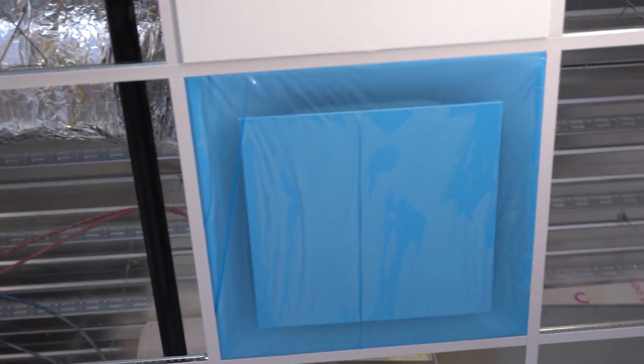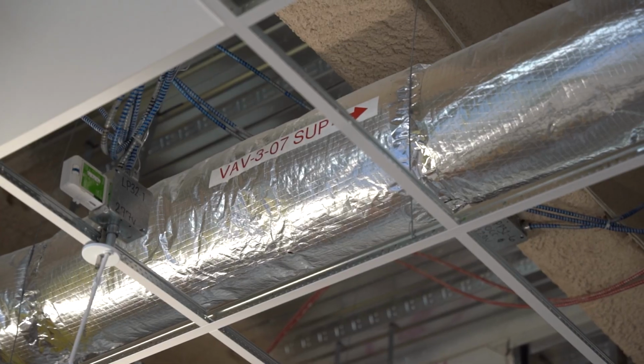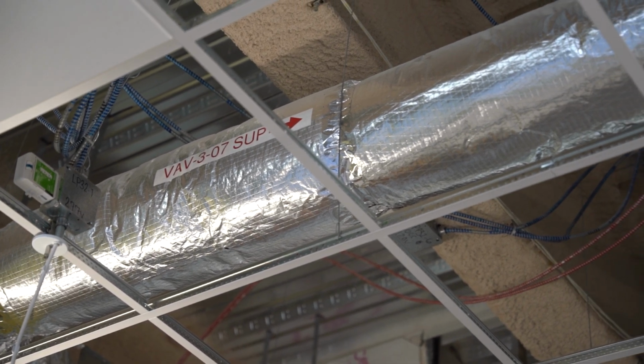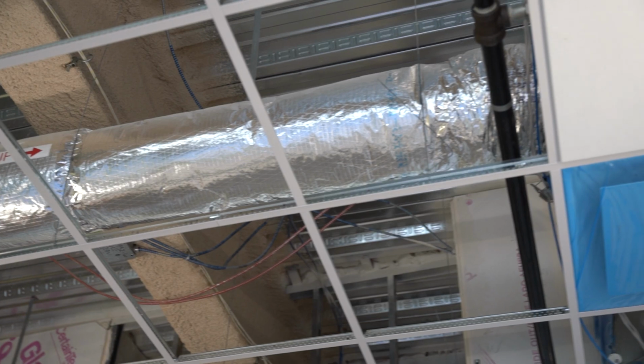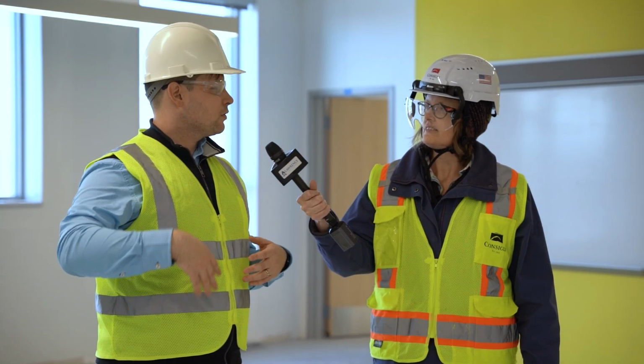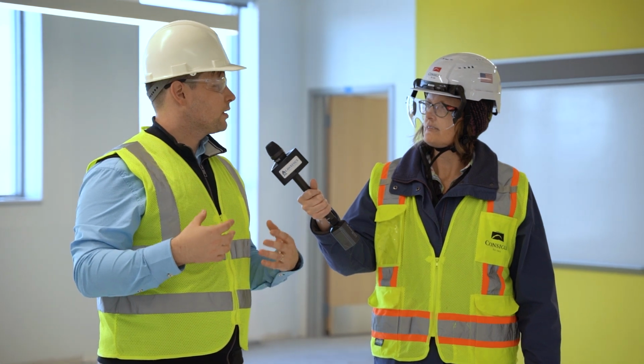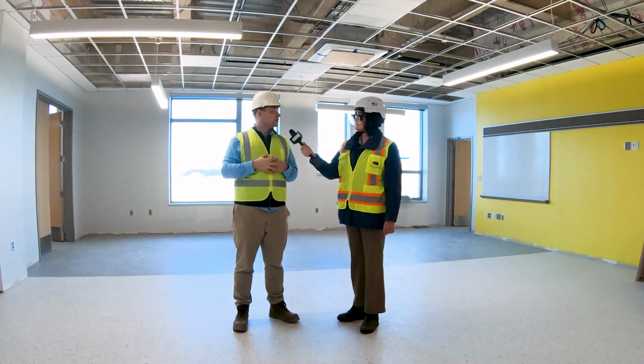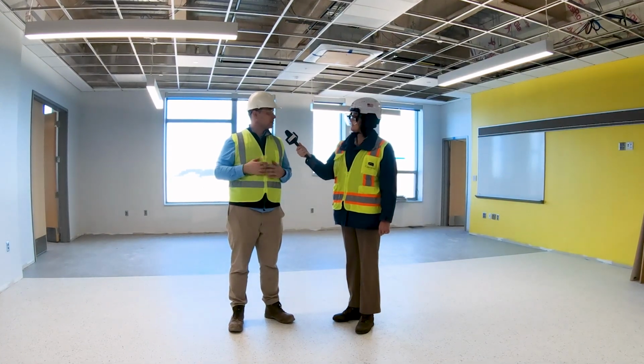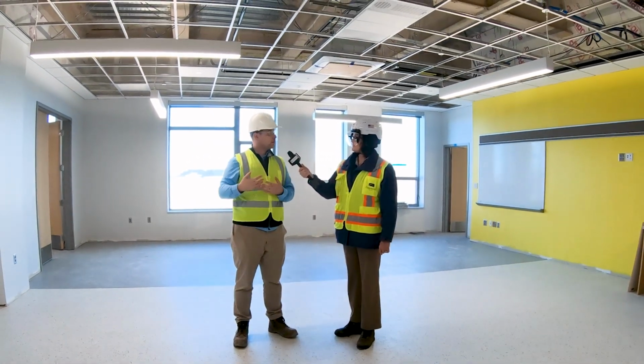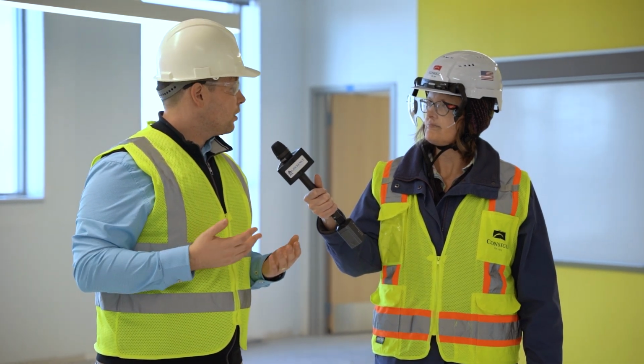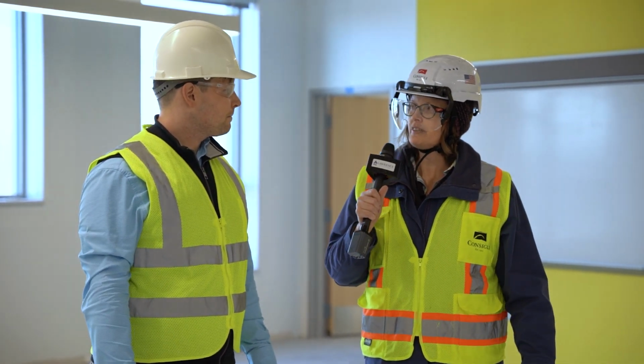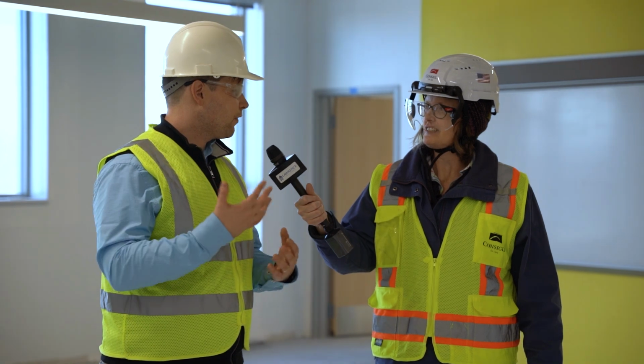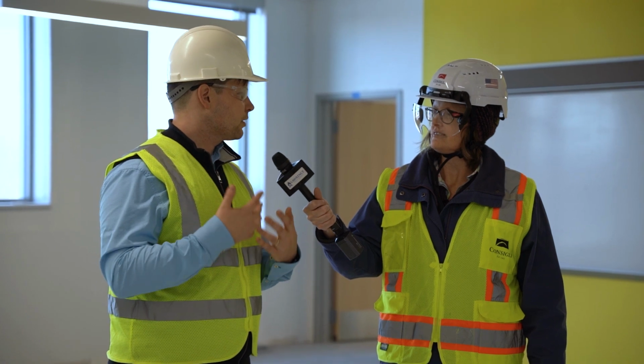What happens when there's not that many people in the classroom? How does the HVAC system know? In this school, we're using demand control ventilation, which is a fancy way of saying that we're having a system check how much CO2 people are breathing out. And as those values increase, the amount of ventilation provided into the space increases. That way, the VAV system can modulate the air up and down based on how much is needed, because sometimes classes are occupied, other times the students go to lunch, the teachers go to lunch, and we don't need as much ventilation anymore. Well, we were talking about modern buildings, but you really don't think about that when you're talking about what you're breathing, but that's pretty amazing. Yeah, we are always trying to focus on how we can save energy, but in a way that still provides the maximum amount of comfort and safety to the occupants.